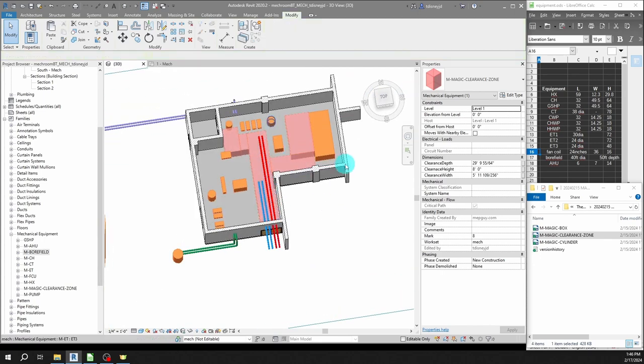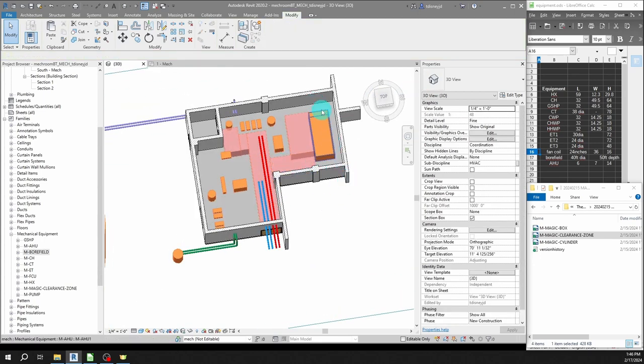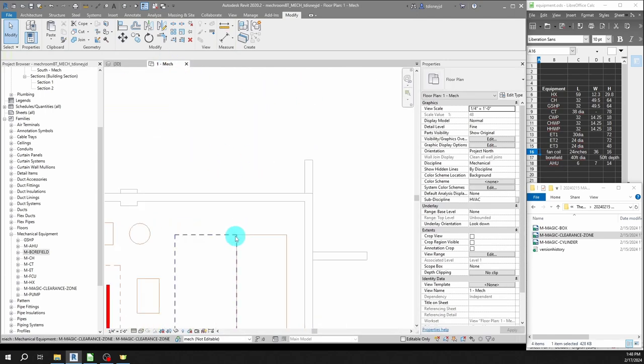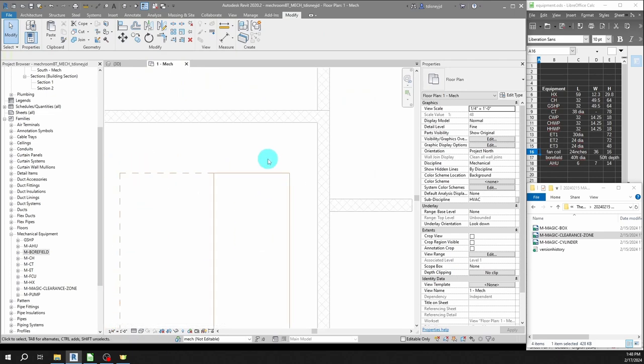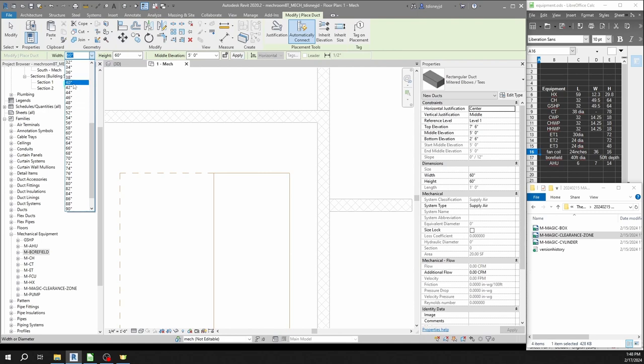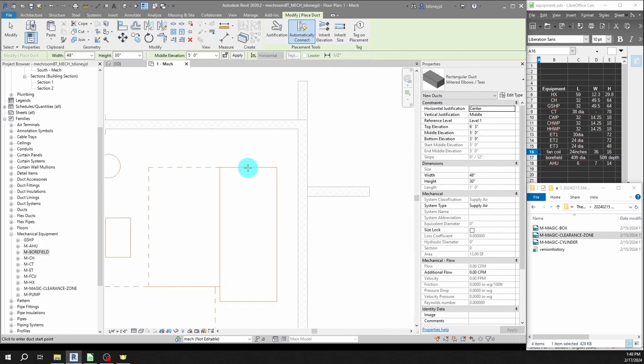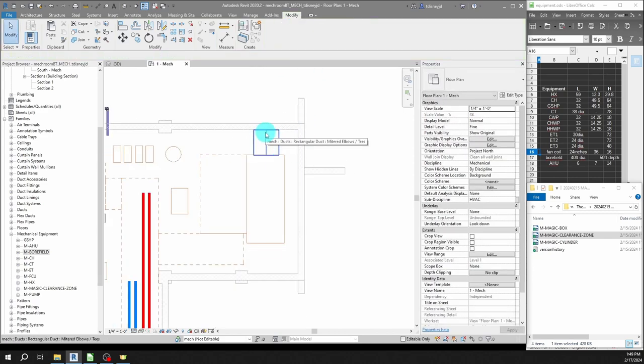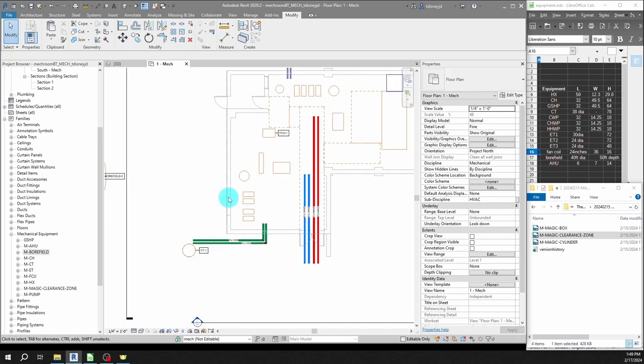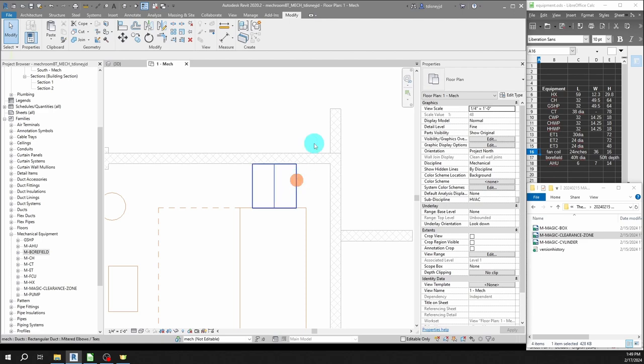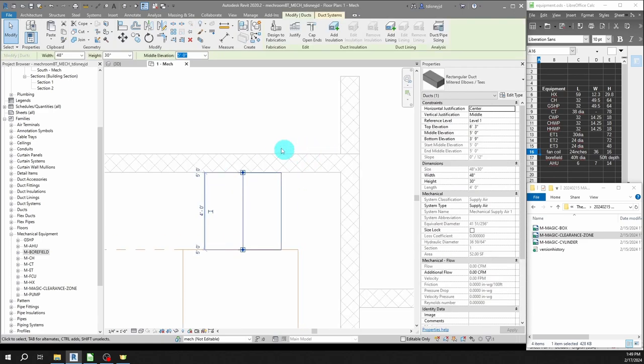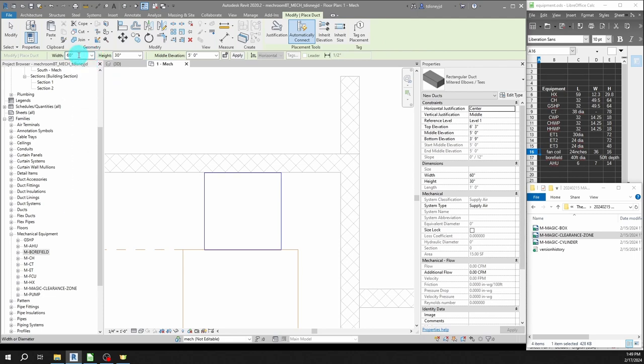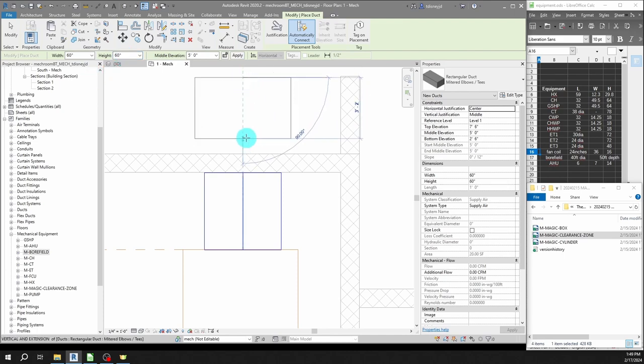Last thing I'm going to do is rough in some ductwork for my air handler. I'm going to draw my duct here, and this is going to be something like 48 by 30 coming out of the air handler. This is another point of coordination with the architect. I need to cut out here for a louver - the architect would give me one here, but I don't need it here, I need it here. This is just the duct connection though, I'm going to have a plenum. I'm going to model in a bit of duct so that they know the size that I need. I'm going to make it 60 inches by 60 inches. I've decided that's how big I want my louver to be, so my plenum is going to be 60 by 60.